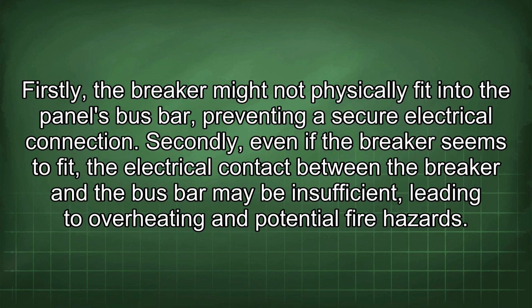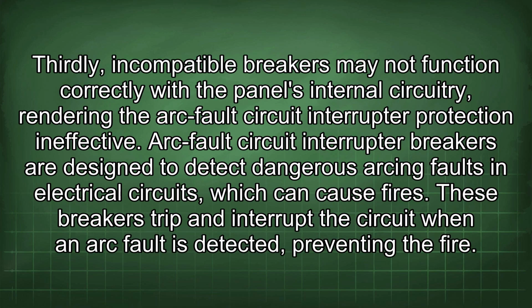Firstly, the breaker might not physically fit into the panel's bus bar, preventing a secure electrical connection. Secondly, even if the breaker seems to fit, the electrical contact between the breaker and the bus bar may be insufficient, leading to overheating and potential fire hazards. Thirdly, incompatible breakers may not function correctly with the panel's internal circuitry, rendering the arc fault circuit interrupter protection ineffective.